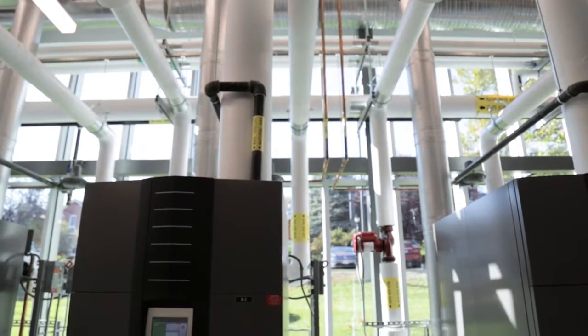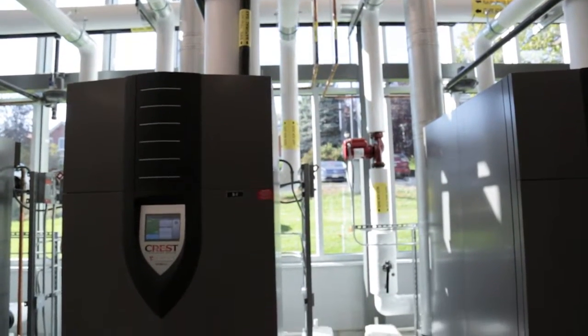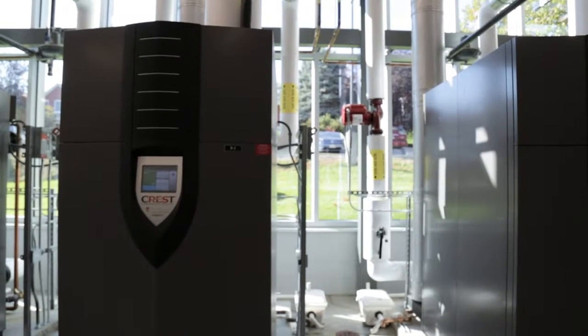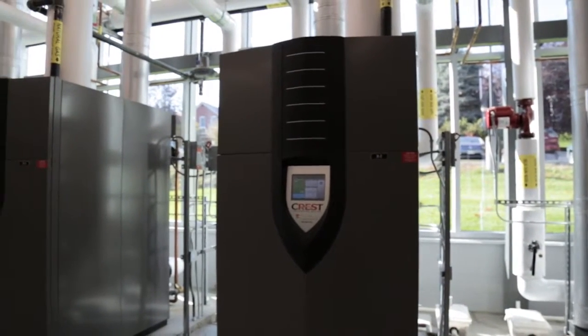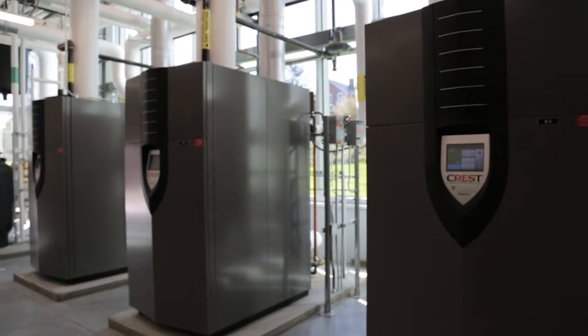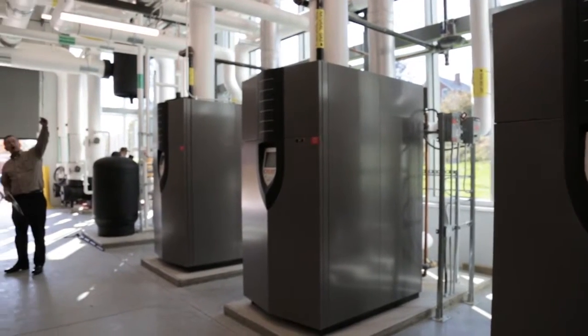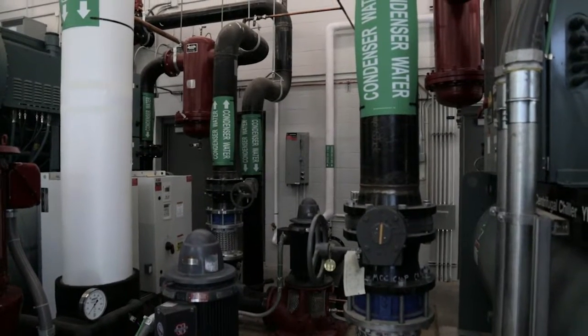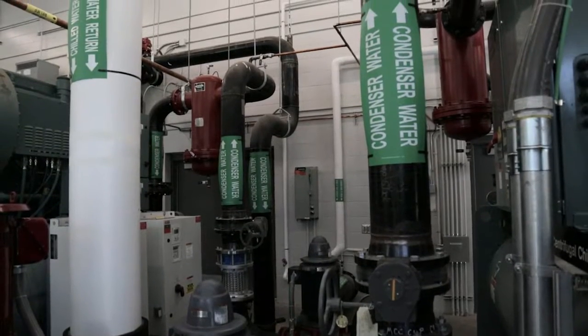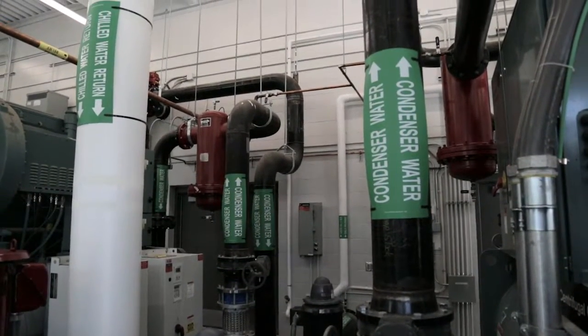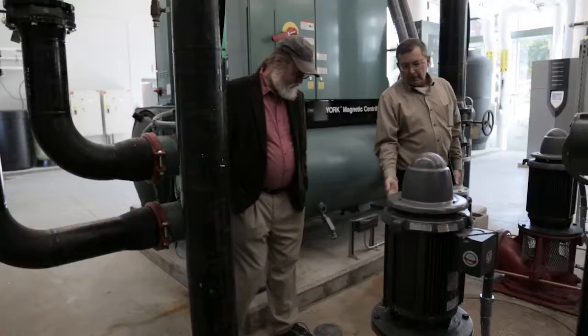What's installed in the Central Utility Plant to serve these three buildings is a system for making heating water - these are our boilers, and on the right you can see three million BTU per hour boilers that generate heating water, pumped through the underground piping system out to each building. On the left are two 500-ton electric-driven centrifugal chillers, which generate chilled water that's piped to each building for cooling.